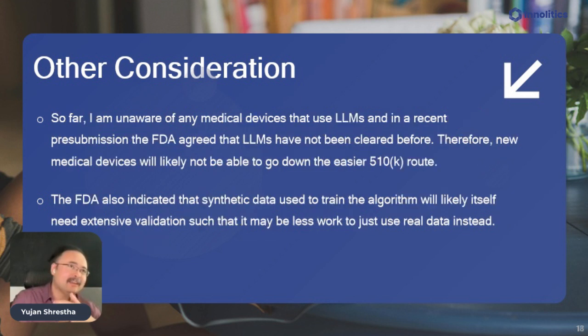So far, I'm aware there aren't any medical devices out there that use LLMs. And we actually did a pre-submission with the FDA where we presented a device that does use an LLM, and the FDA seemed to corroborate my thought that there haven't been any LLM cleared devices yet. Therefore, any new devices going down this route probably will not be able to use the 510K route, which is generally accepted to be the easiest way to get medical devices cleared here in the US. And they can't go down the 510K route because there is not a suitable predicate for that.